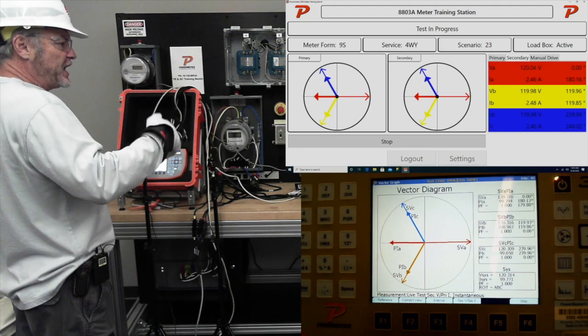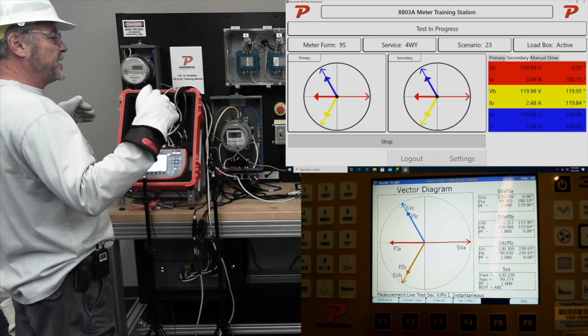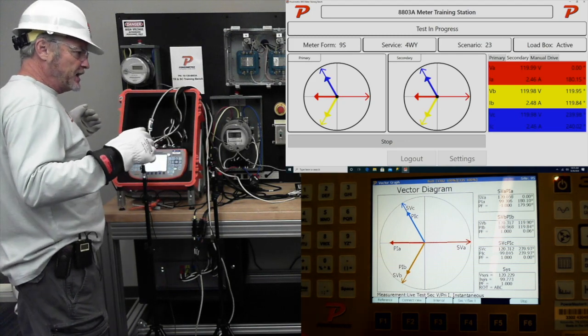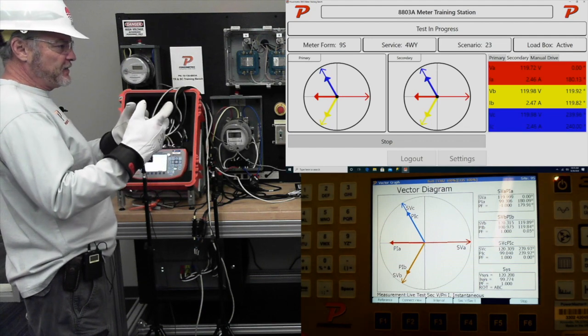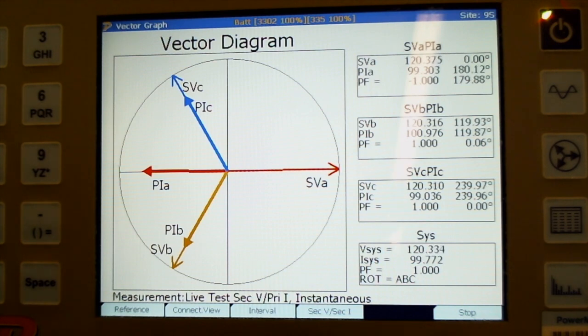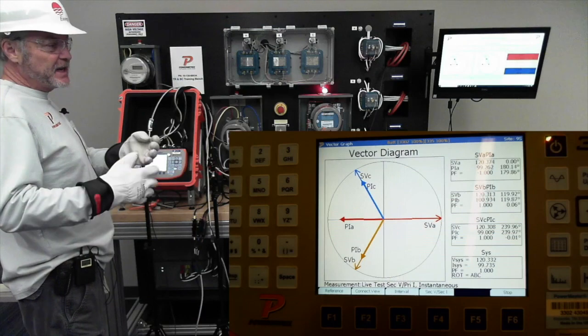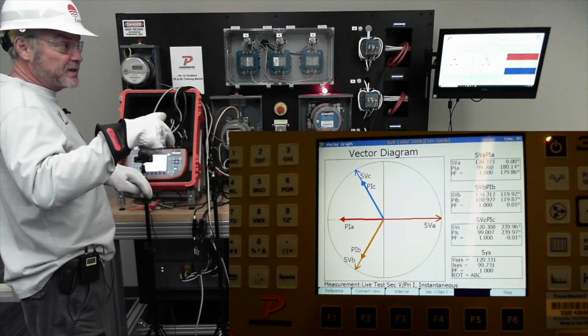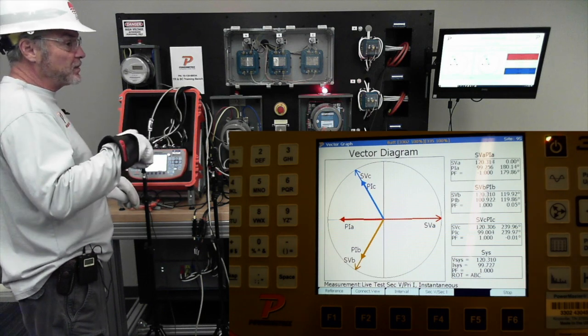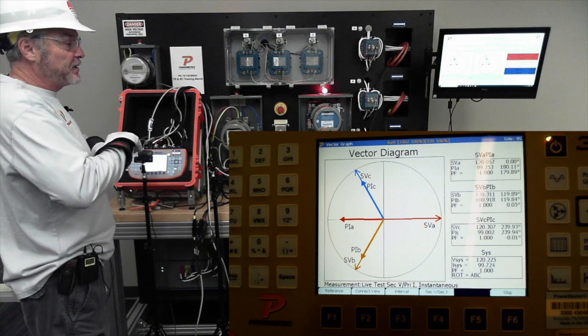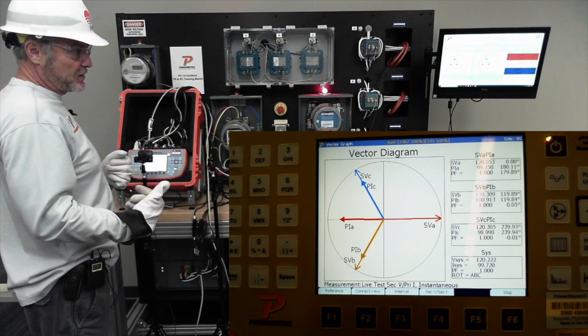I didn't get any change between my primary polarity reversal and my secondary polarity reversal. Remember, one of the tricks we use out there, an excellent tool, is if I go to that primary vector and the primaries look good, then go back to the secondary vector and it shows polarity reversal, chances are those secondary wires are swapped on that CT. But if, like I just did here, both primary and secondary show polarity reversal, then the problem isn't on the secondary we initially saw on the machine. The real problem is on the primary, which we found by toggling. So in this case, I'd say I have polarity reversal on the primary, not the secondary.